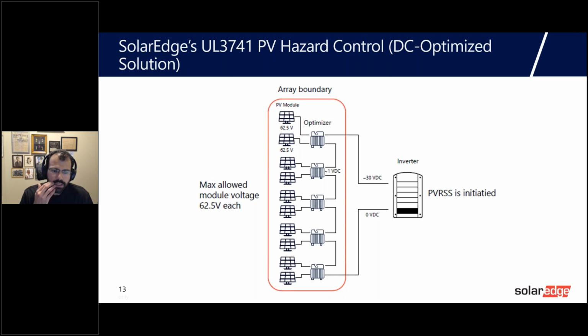Cool. Okay, so let's take a quick look at our solution, the SolarEdge solution. How it works: DC optimized systems, which are systems with DC optimizers and inverters, allow for 2 panels to be connected in series, meaning that upon rapid shutdown initiation, the maximum voltage within the array is 125 volts DC. That's the open circuit voltage of 2 modules in series. As a result, the systems fall within hazard level 1 or lower inside the array boundary, eliminating the need for additional protective measures to comply with 3741. 3741 compliance is built into our optimizers and inverters and requires no extra parts.